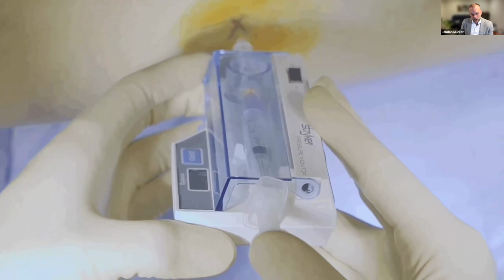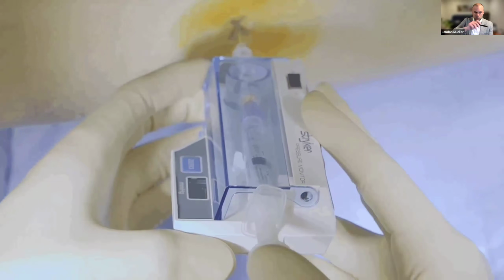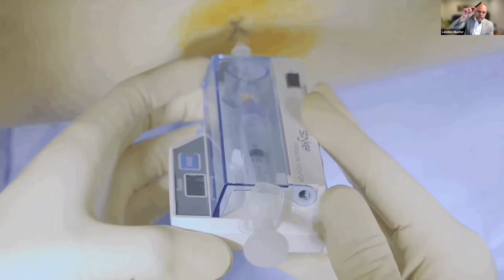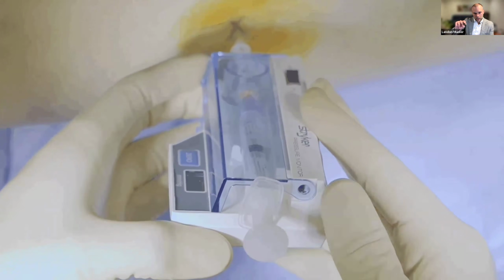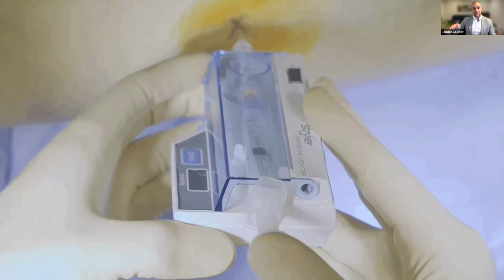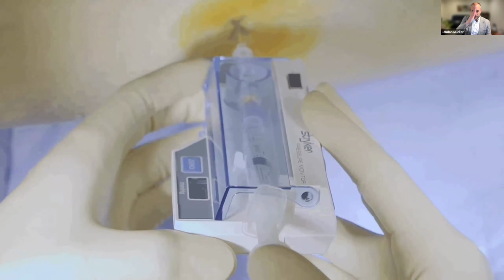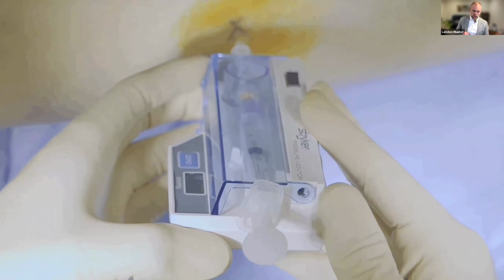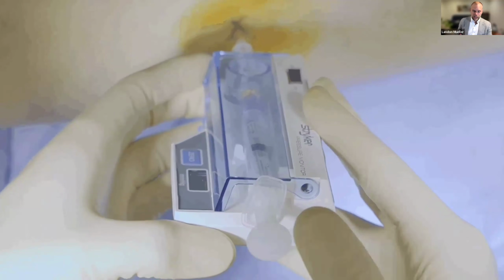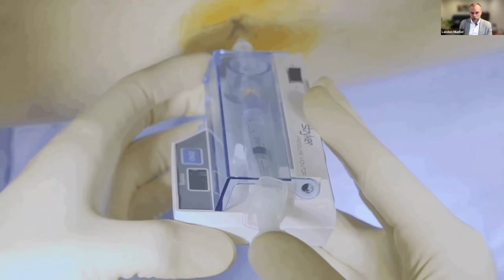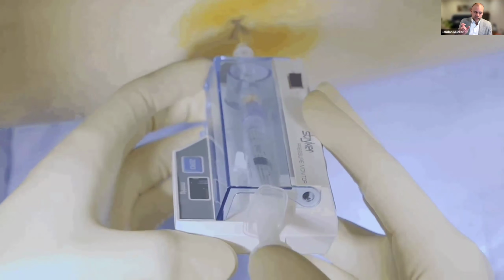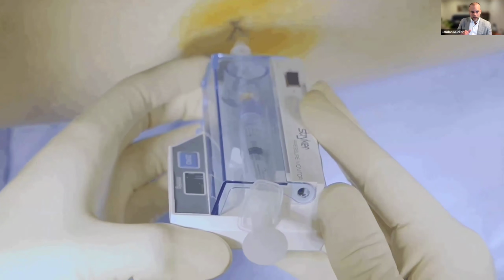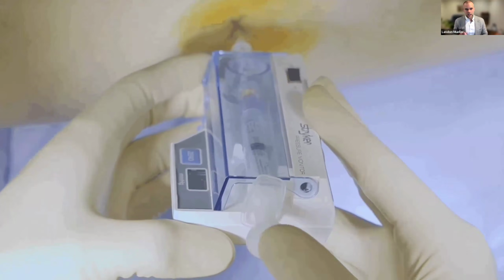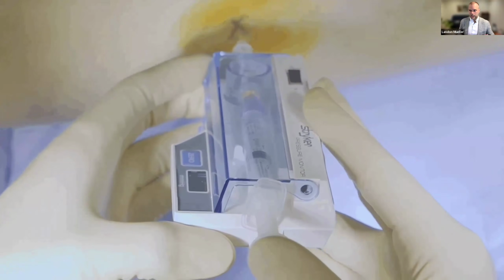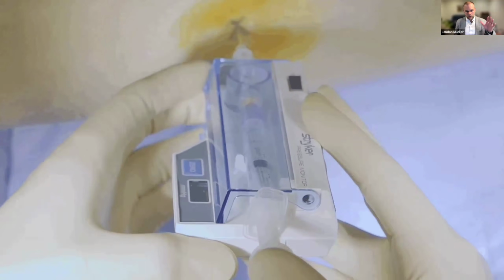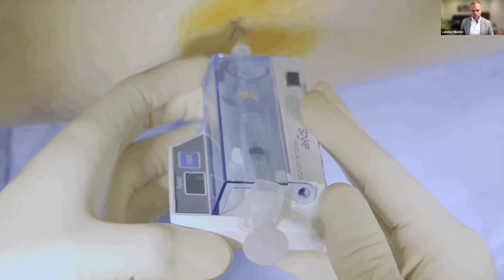Typically, when you do that pulse, there's a sharp increase in the pressure. So it may jump up to, we'll just say 30, and then it starts to tick down: 30, 29, 29, 28, 27, 27, 27, 27, and it stays level for a few seconds. That level number, once it's come down, is what you're looking for. So that is the whole process of how you do it. It's pretty simple once you've done it a couple of times, as long as you remember a few key things: zeroing the device in the correct 90-degree orientation that you're about to enter the skin, and then getting a feel for what the device looks like after you pulse the fluid and measuring that pressure as it comes down.